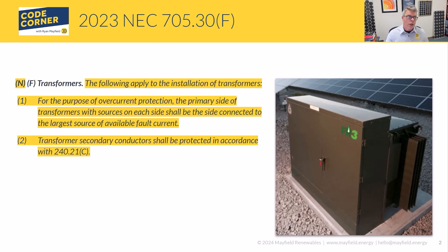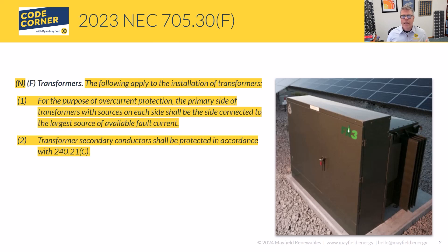Number one talks about the primary and secondary side of the transformers. This is important because we often get associations of primary and secondary with voltage levels. In a traditional commercial/industrial installation, the utility might come in at 480V and we need single-phase loads at 120V. So we take a transformer and step 277/480V down to 120/208V for the loads. In that case, the primary is the 480 side, the secondary is the 120/208 side.